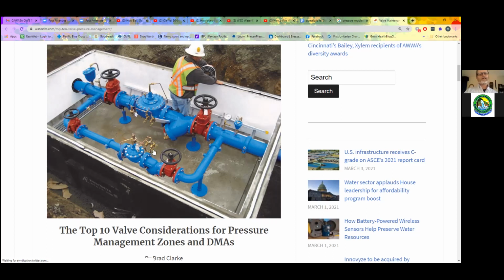You can see, though, that what will happen is that when this is connected to the downstream, if there's a demand, a lot of times the smaller valve, without knowing for sure, we'll say this is a 4 and an 8, could be a 3 and a 6-inch diameter, 75 millimeter, 150. This will open first and supply the demand downstream. And because these are also check valves, it's not opening and going back up. They will be set. You can see where they've got pressure gauges ready to go, pressure gauges above and below the valve. And so as demand increases, this valve will open up further and further.